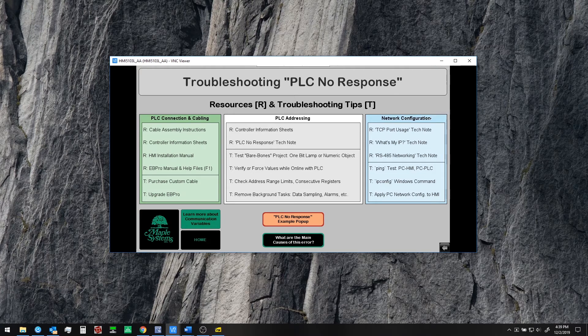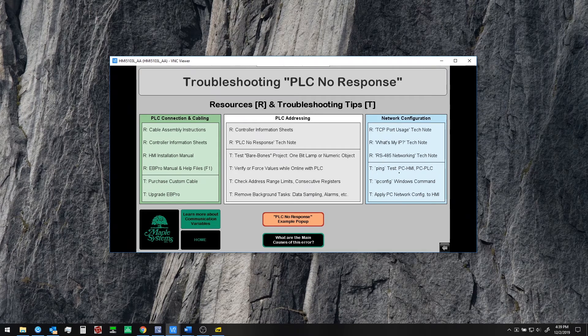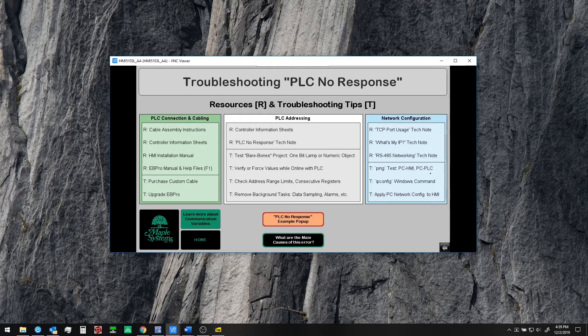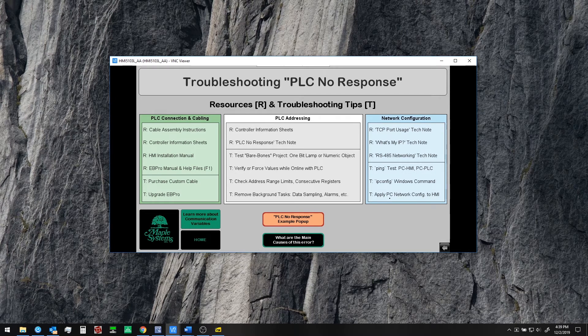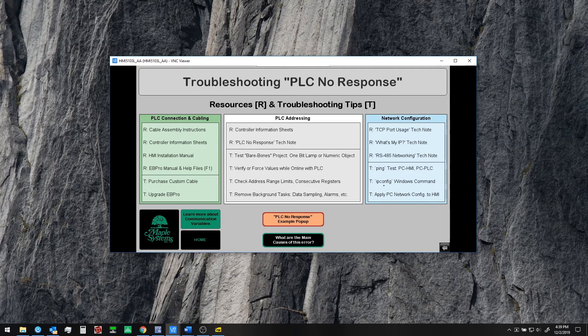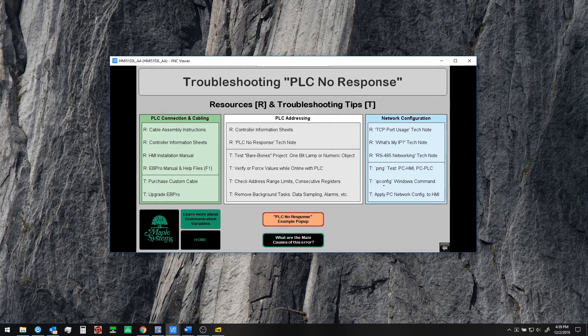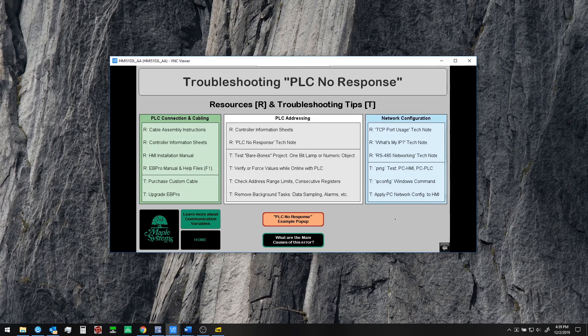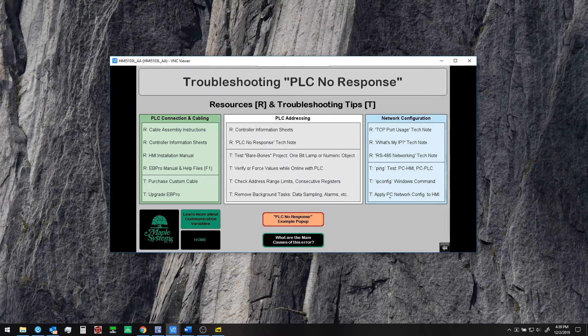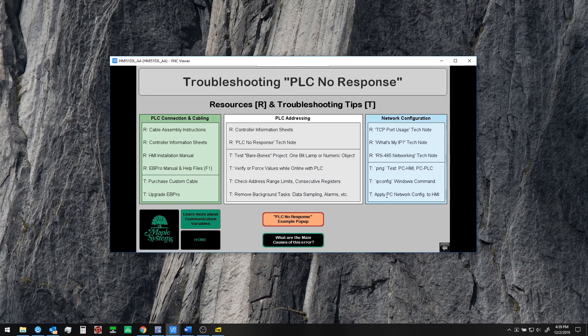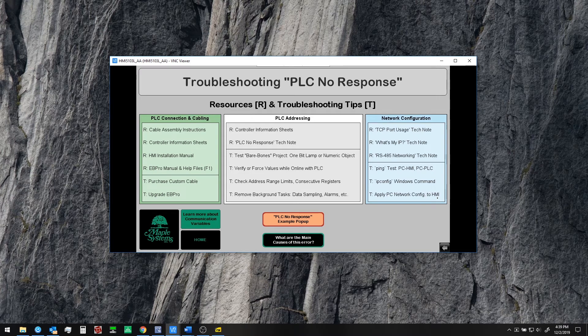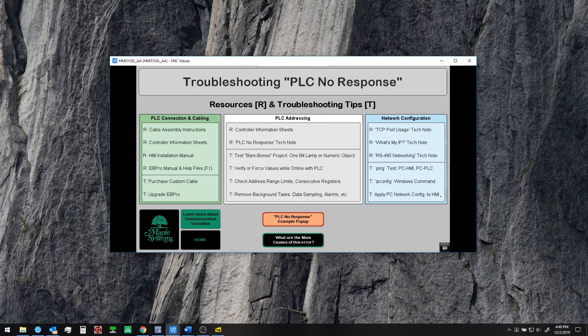On the networking side you may use the ping command test the connection between your PC and HMI and between your PC and PLC. And another idea here is if your PC can talk to your PLC but your HMI can't run IP config or look at all of your network interfaces how they're configured. Make sure you know which one is in use for talking to the PLC directly. Is it Ethernet or Wi-Fi for example. And then put your HMI into the exact same configuration as your PC has. Sometimes that can do the trick. So you maybe take your PC offline but you apply the exact same IP address subnet and gateway to your HMI and restart it. See if you get your communication established with your PLC at that point.